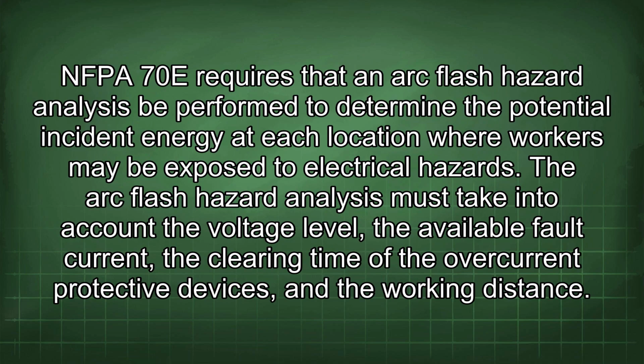NFPA 70E requires that an arc flash hazard analysis be performed to determine the potential incident energy at each location where workers may be exposed to electrical hazards. The arc flash hazard analysis must take into account the voltage level, the available fault current, the clearing time of the overcurrent protective devices, and the working distance.